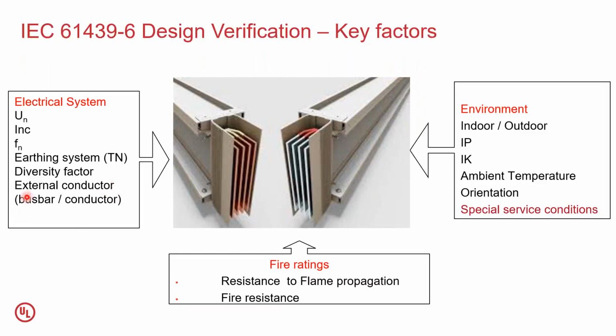Then you also need to know what the external conductor connection, or so-called field conductor, is going to be meant for. Is it meant for bus bar, or for both bus bar and conductor cables, or is it only for cables? That has to be decided, and this is one of the key attributes for the specifier, the manufacturer, and also for the test lab.